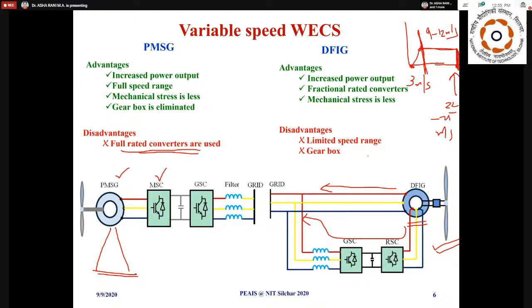DFIGs can generally operate at a slip of plus or minus 30%. So if the stator is pumping power P, the rotor can pump an additional 30%, since the rotor power equals slip times stator power. If stator power is PS, the rotor provides slip times PS, which is 30% of PS. So PS plus 30% of PS is pumped to the grid—meaning DFIG is capable of generating 130% of rated power, more than the machine's rated capacity.